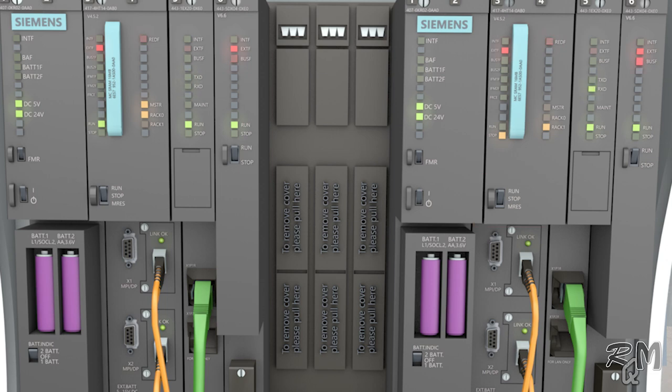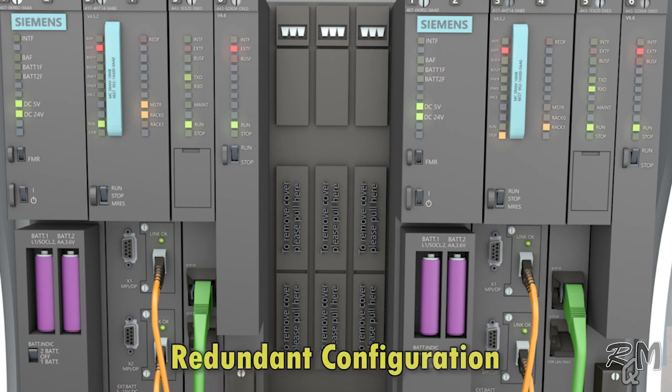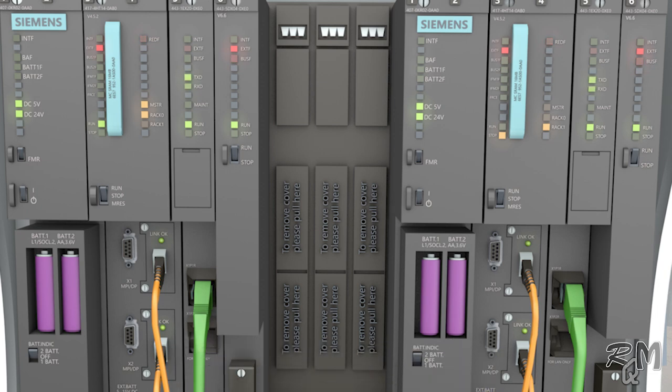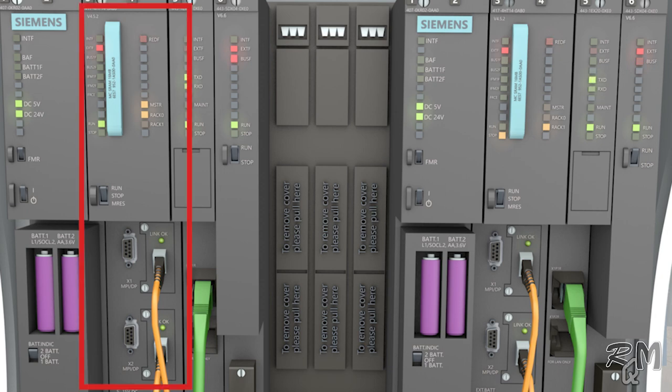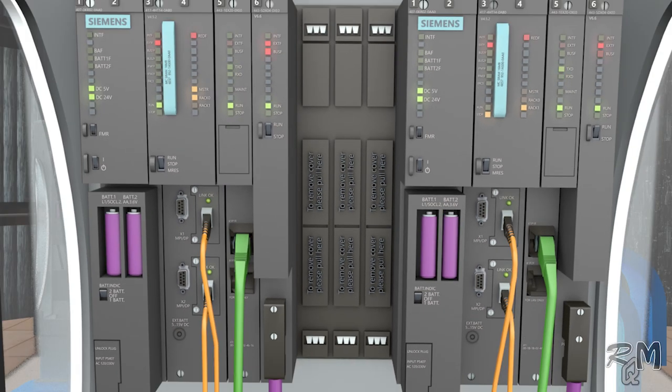To handle this type of situation, I am going to show you a simple method which can restore redundant CPU easily. Before applying this method make sure that both S7-400 CPUs are installed and configured as redundant. There should be no other fault LED on in both CPUs. Only external fault can be ignored. Active or master CPU should be healthy and managing control system properly. Fiber optical patch cable link 1 OK and link 2 OK ready should be green. Then you can restore redundant CPU or memory card of CPU easily.